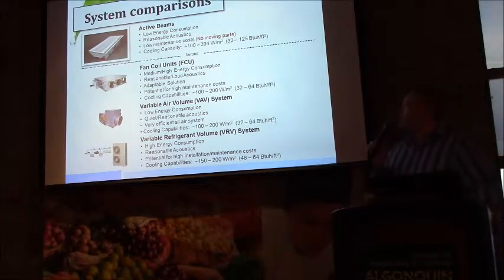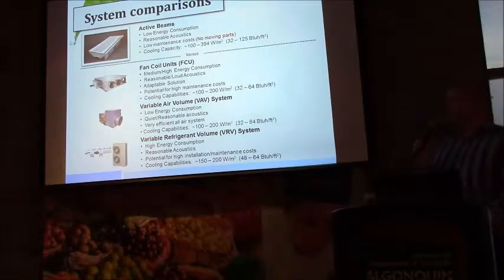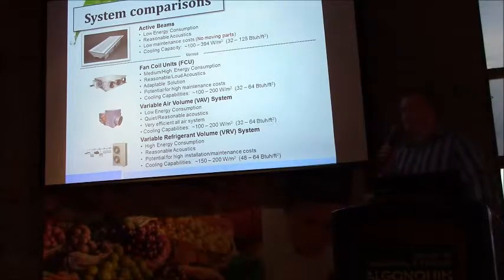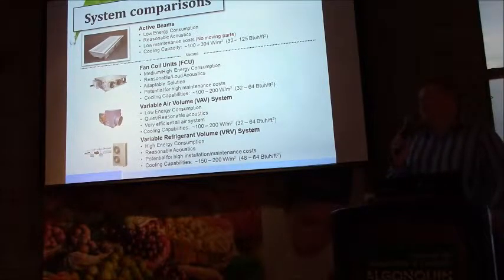So once a decoupled ventilation system, we've seen them before, fan coils that are operated dry, where we're introducing the minimum primary air, would fundamentally use the same design principles relative to offsetting the latent loads in the space. Variable air volume systems obviously can also create a more efficient air delivery system by modulating the airflow. And then the VRF and FCUs, or fan coil units, are effectively the same except for the operating fluid, one being chilled water, one being volatile fluid refrigerant.